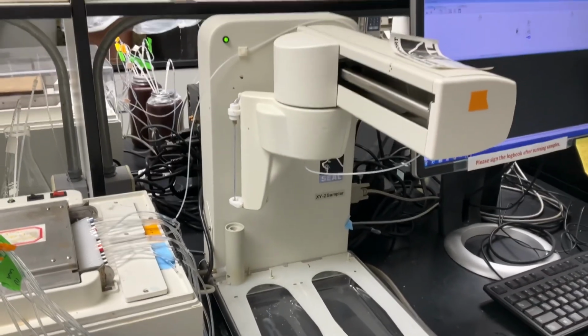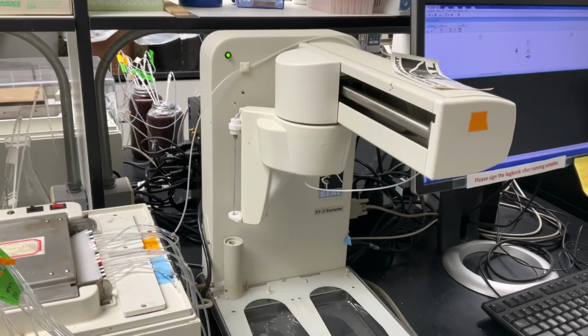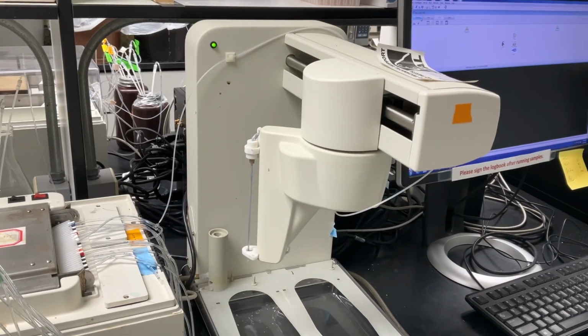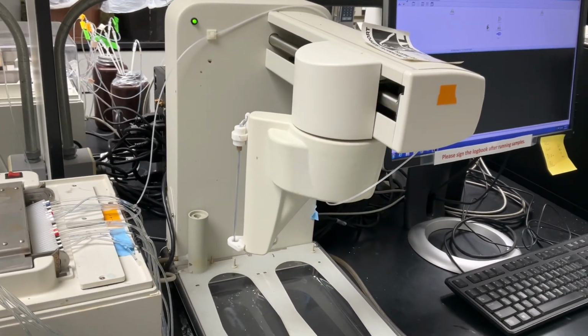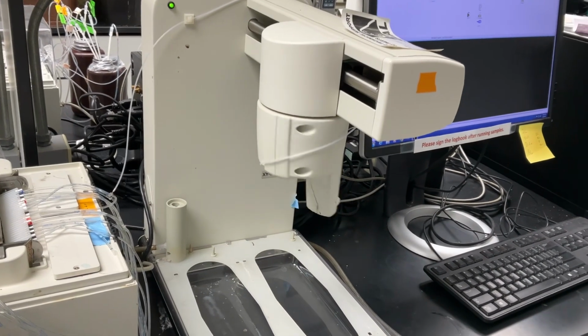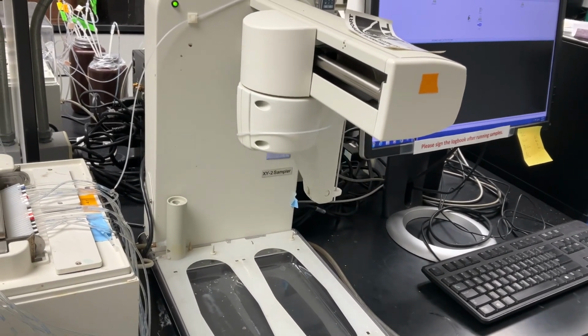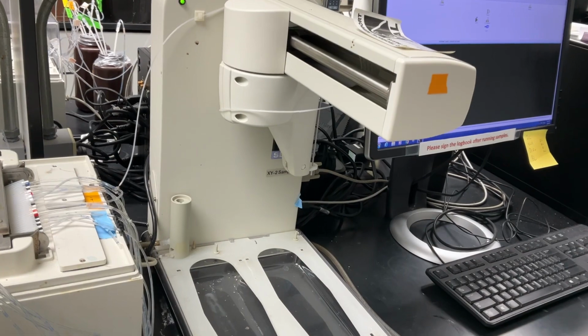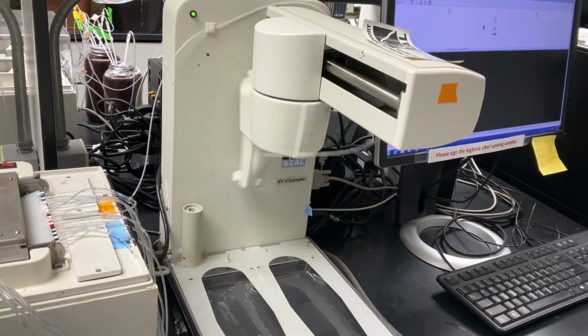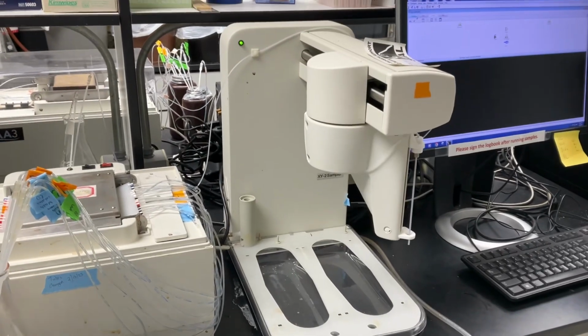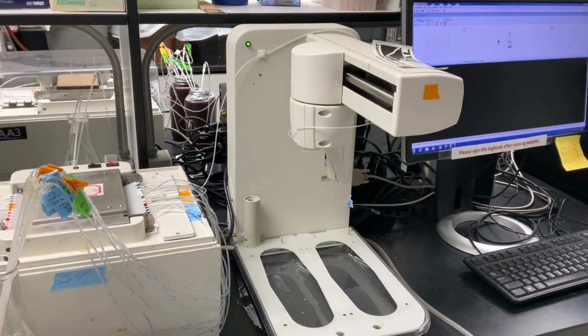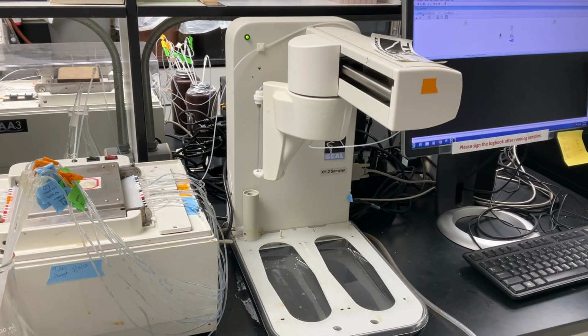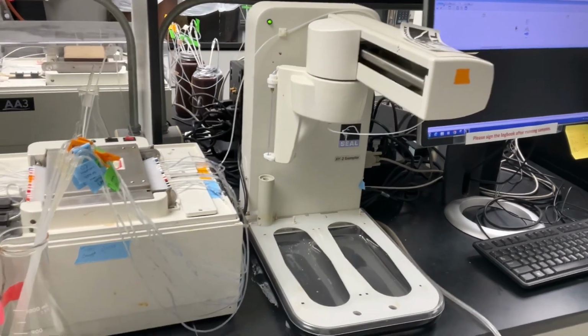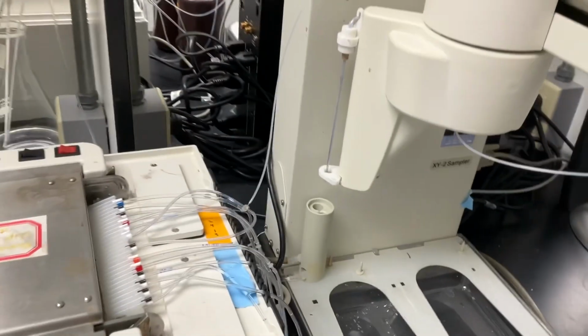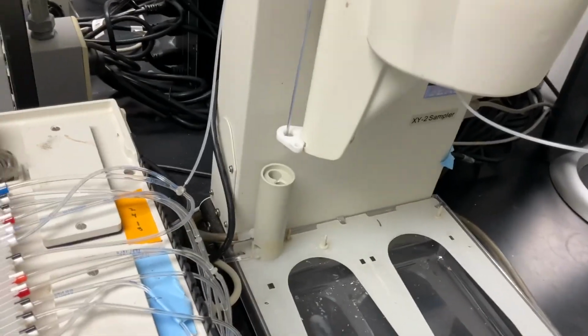As you can see, that starts moving the probe around as it calibrates itself. The arm actually is going to move to all of the furthest positions that it can to either get to a cup sample or to get to a standard stock solution. So it kind of has this full 360-degree calibration test just to make sure there's nothing in the way. If the arm does hit anything while this is running, the machine basically just stops all functionality. I haven't found a way to get it to start on its own other than a hard reset, so if you're ever actually running your samples, you've got to be really careful not to bump into that arm.